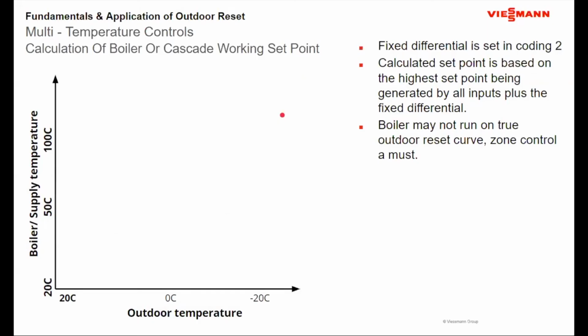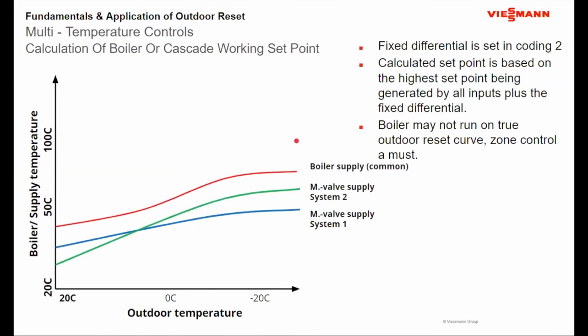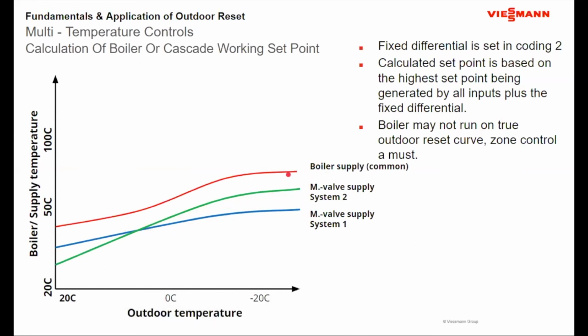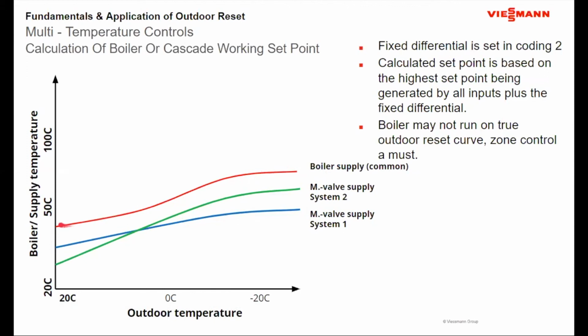So what you may end up with from a boiler standpoint, let's say I have two mixing valves. This happens to be one mixing valve with this heating curve. This green line is the second mixing valve heating curve. But what happens is the boiler maintains its differential temperature, this 14 degrees, always above and beyond the mixing valves. So you notice I have two nice smooth curves set, but when I look at my boiler control, the boiler control curve is not smooth because the boiler control is trying to maintain the right differential above each one of these mixing valves. These could be mixing valves. It could also be a set point in there. There could also be another heating curve for high temperature as well.